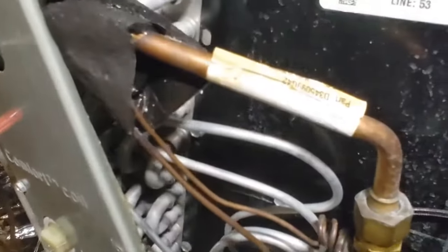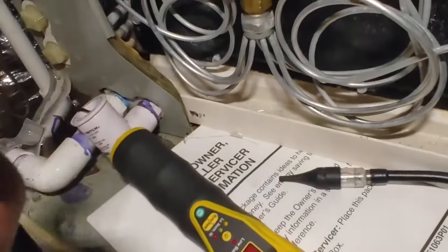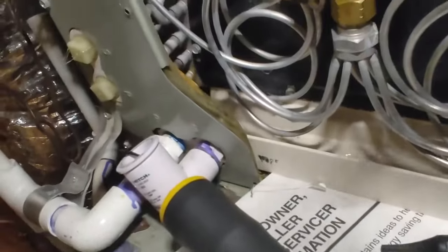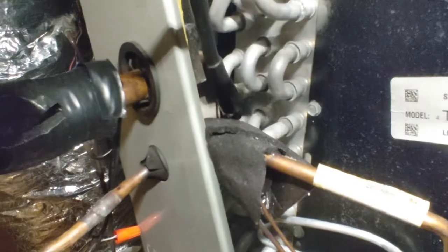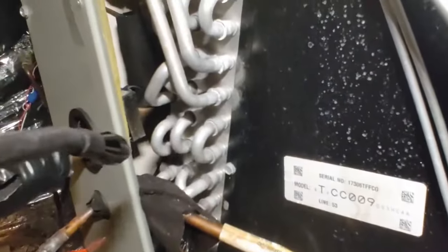I just found a leak in a 2017 Trane coil using my AccuTrak ultrasonic leak detector. I wanted to give you an idea of what it sounds like when I'm pinpointing this thing. It's actually pretty decent. I've got my headphones here by the mic, so this will work. You can hear it coming in clearly.